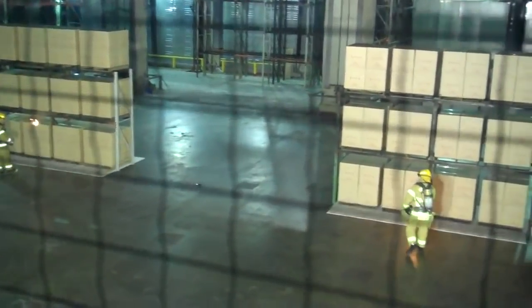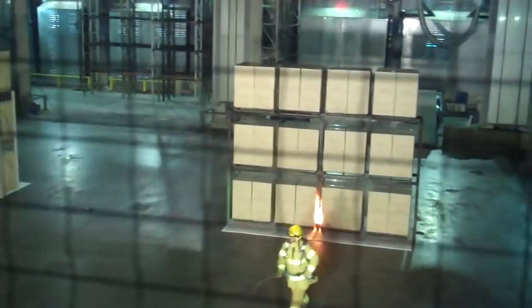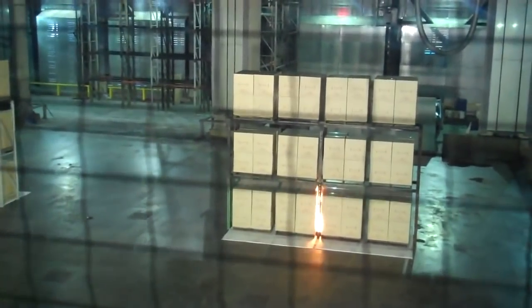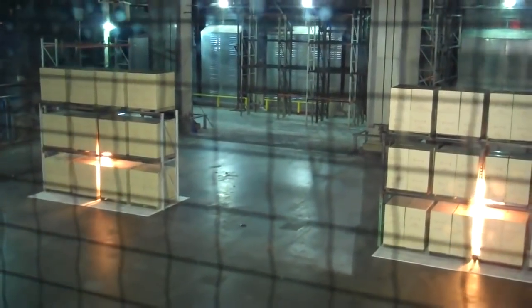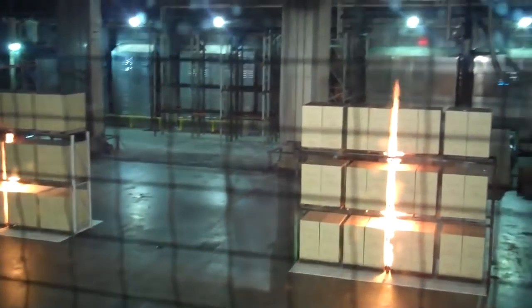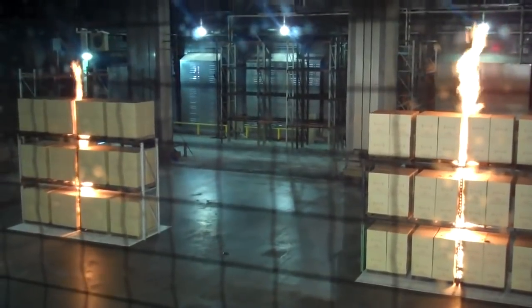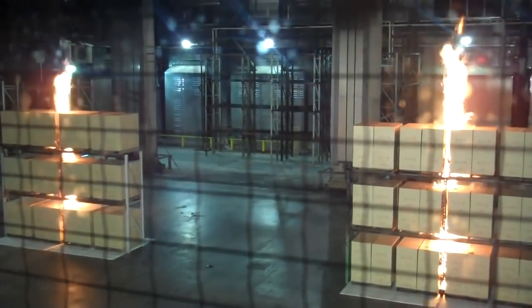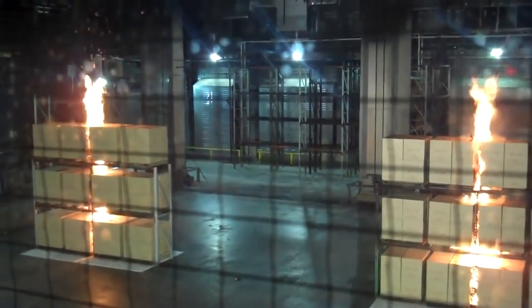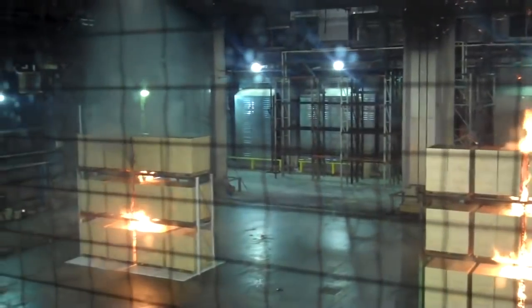They just passed off control of the fire to the guys on the floor. We have ignition. We have 250 degrees at the ceiling. Sprinkler operated — sprinkler operated 48 seconds into the test.